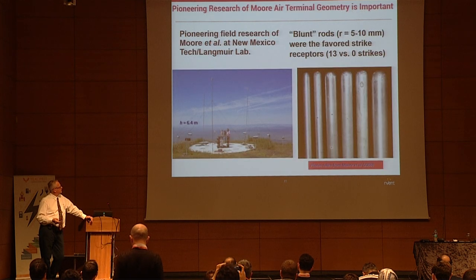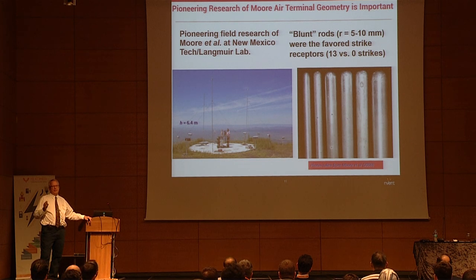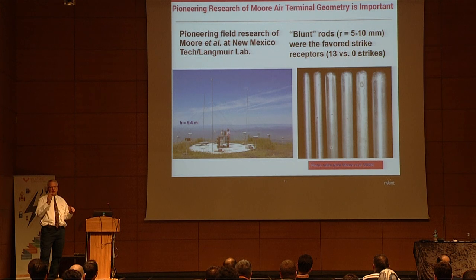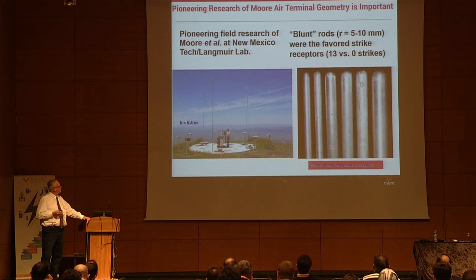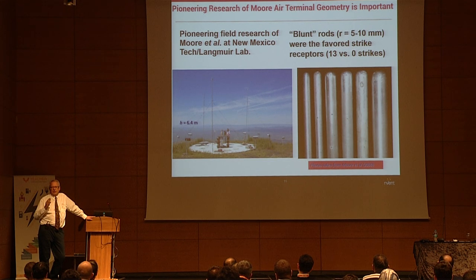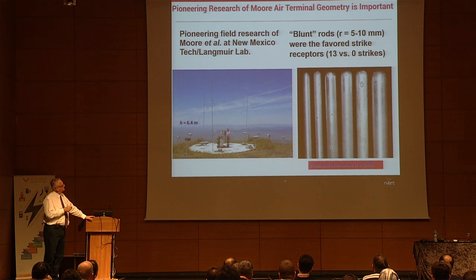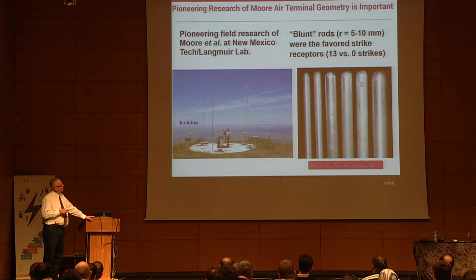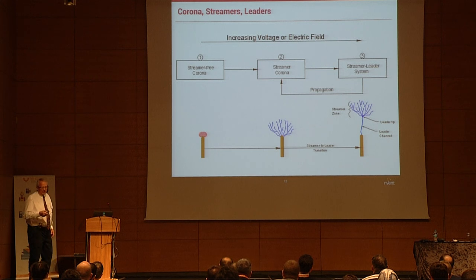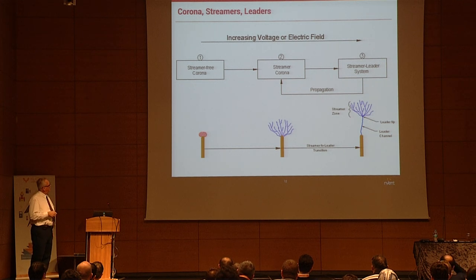What's also important is optimizing the formation of corona, which is the first step in lightning protection when the field intensifies. Dr. Moore studied this at high elevation in New Mexico, proving that a blunt radius between 5 and 10 millimeters took all the strikes, while sharp points did not. This is streamer-free corona — just corona above the lightning protection terminal.